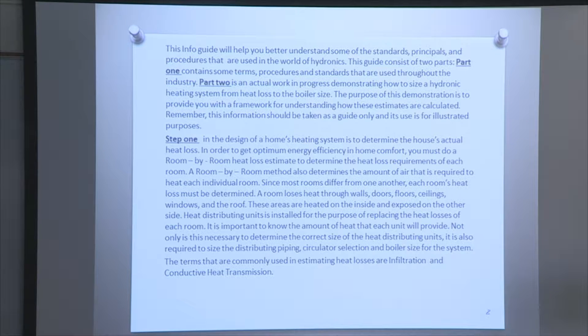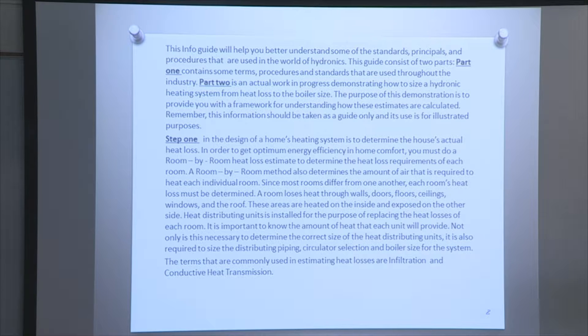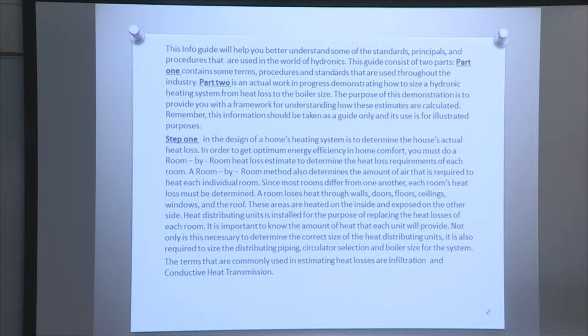These areas are heated on the inside and exposed on the other side. Heat distribution units are installed for the purpose of replacing the heat losses of each room. It is important to know the amount of heat that each unit will provide. Not only is this necessary to determine the correct size of the heat distribution units, it is also required to size the distribution piping, circulator selection, and boiler size for the system. The terms commonly used in estimating heat losses are infiltration and conductive heat transmission.